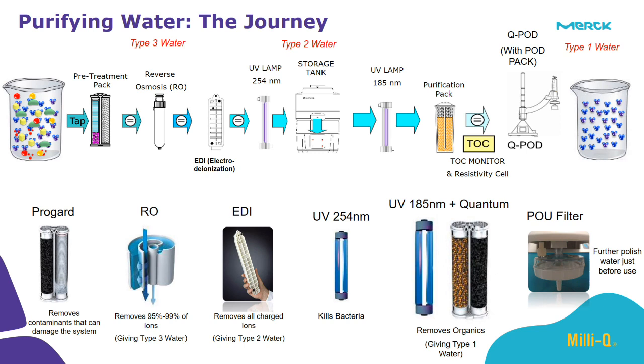The water is then followed by a UV lamp of 185 nanometers and a purification pack called Quantum, which gives us type 1 water by removing any remaining ion contamination, and then followed by the dispenser, which is Q-POD, also fitted with a 0.2 micron membrane to make sure that we have type 1 water at the end point of the system.